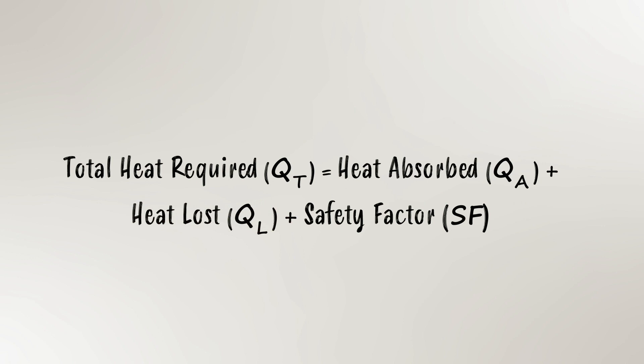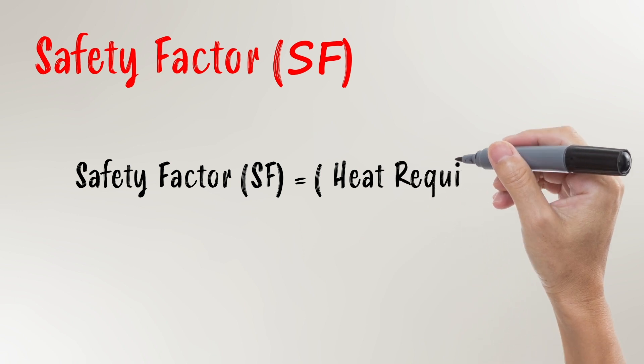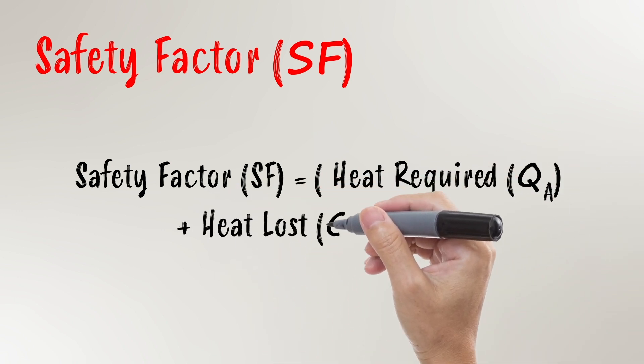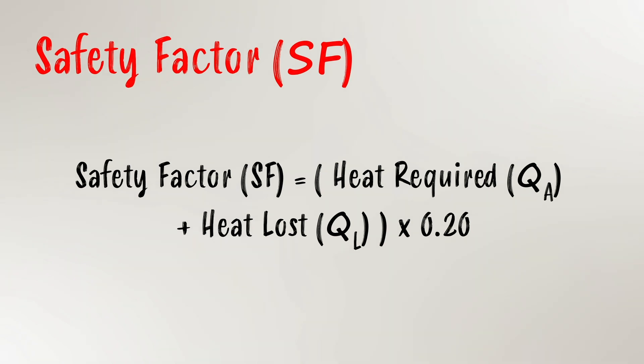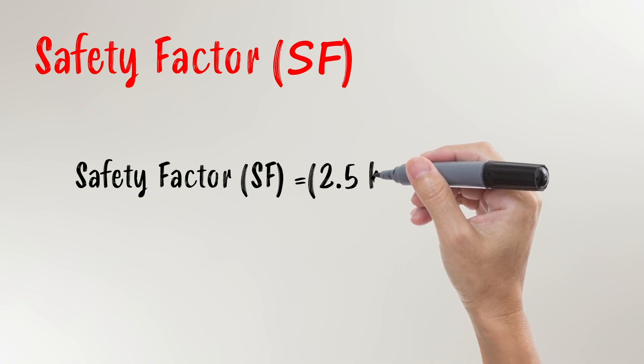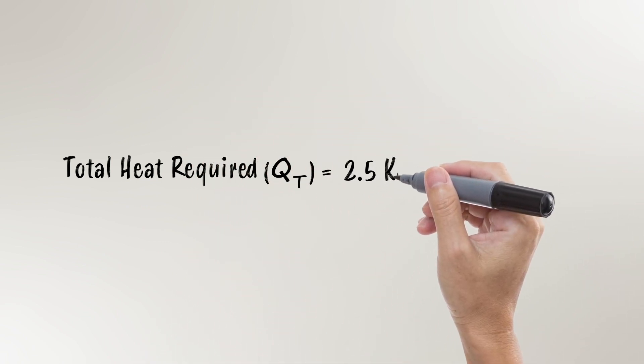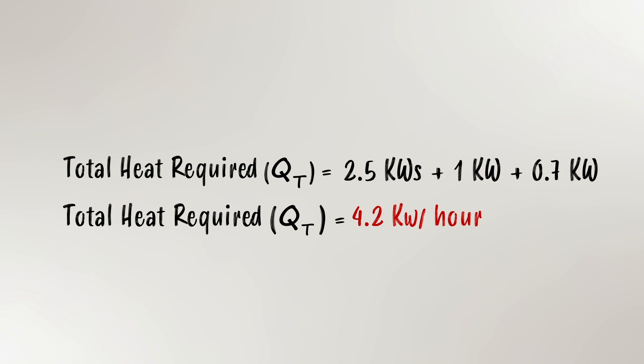Time to move on to the final component: the safety factor. This component ensures that you'll have more than enough energy available for your application. We recommend adding at least 10%, sometimes up to 20% if the conditions are uncertain or there are many unknown variables. You add your QA and your QL values together and multiply by 20%, giving us a safety factor of 0.7 kilowatts. Once you've calculated that, all that's left is to add the three numbers together — and you're done. You have now successfully calculated the total energy required for your heating application. In our scenario, we get a final total of 4.2 kilowatts per hour.